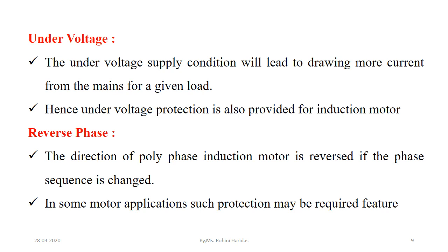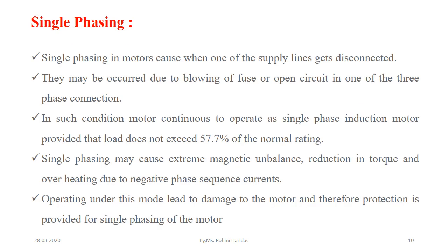The direction of rotation of a polyphase induction motor reverses if the supply phase sequence is changed, so reverse phase protection may be applied in some motor applications. Single phasing occurs when one of the supply lines gets disconnected, due to a blown fuse or open circuit in one of the three-phase connections. In such a condition, the motor continues to operate as a single-phase induction motor, provided the load does not exceed 57.7% of normal rating. Single phasing may cause extreme magnetic unbalance, reduction in torque, and overheating due to negative phase sequence currents.